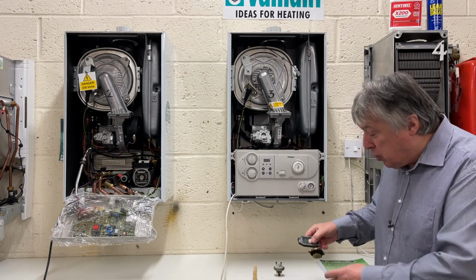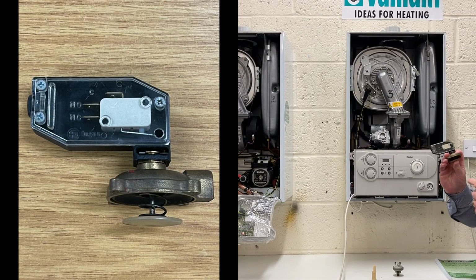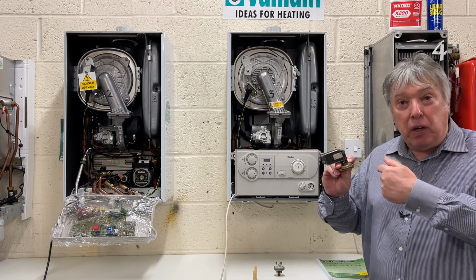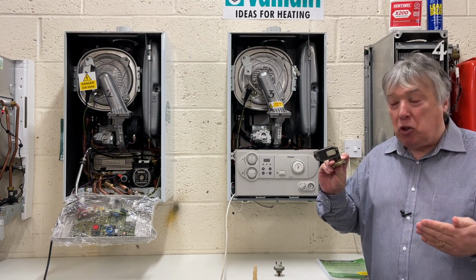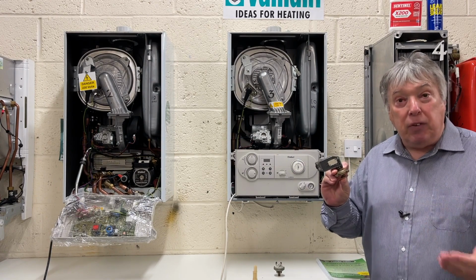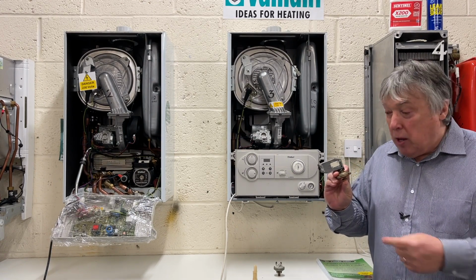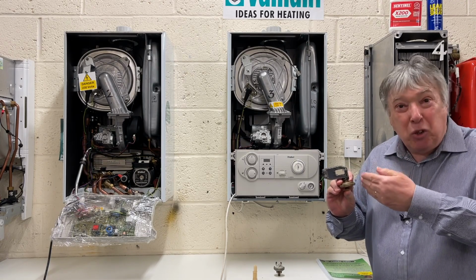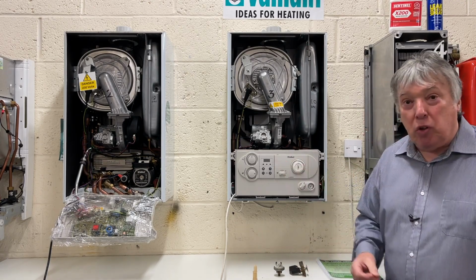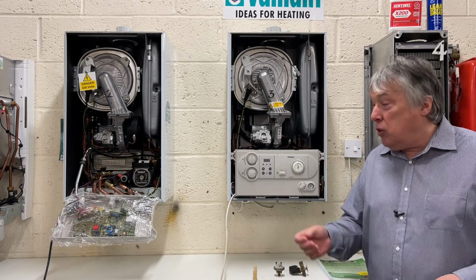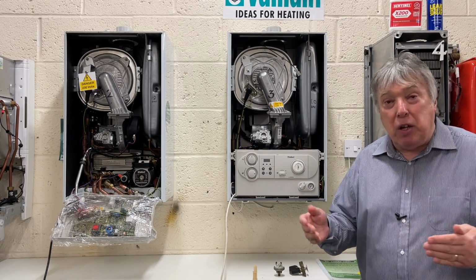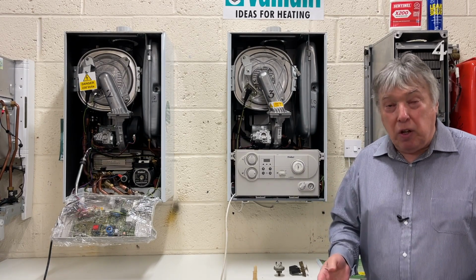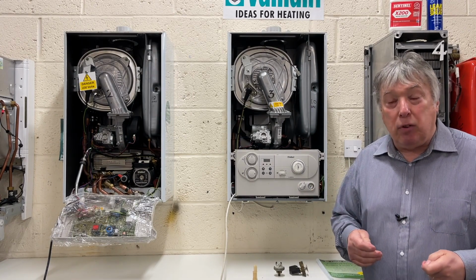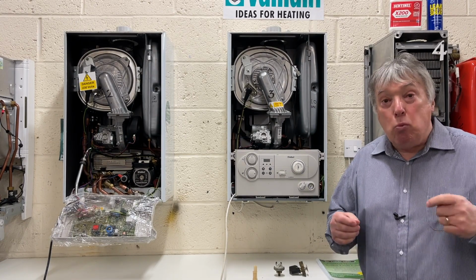If we go back to the older versions, perhaps this will explain. So this is a sort of a diaphragm underneath, and when the pump is activated, it pushes this upwards and makes the contact, and the PCB, etc., kick into action. And when the pump stops, the pressure decreases and everything goes back to sleep and standby mode. This is, let's say, the old-fashioned way of doing it, and now of course we've got sensors. So what I've done is, on the Vaillant boilers, I've listed the top dozen or so most popular faults and tried to explain, to have a look to see what's actually gone wrong and what else to check.